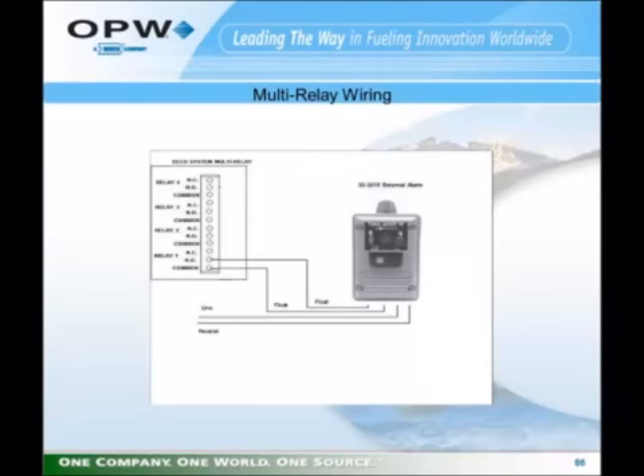For multi-relay wiring to an external alarm, the external alarm unit that we supply has 4 wire connections. One is labeled line, one is labeled neutral. That is a 120 volt supply that goes to that external alarm. And then it has 2 wires that are labeled float. Under normal conditions, one of those float wires would go to the common connection of a relay. The second float wire would go to the normally open connection of a relay. Keep in mind that these float wires, even though they are labeled float, have 120 volts AC on those wires, so be careful when working around these wires. So when the relay energizes, it will change its connection from between common and normally closed to common and normally open and activate this external relay.